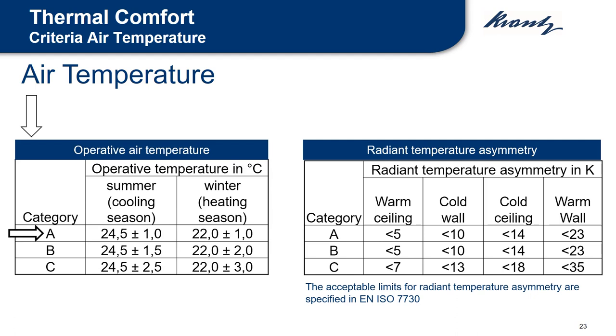In the right table, we can see the allowable radiant temperature asymmetries, likewise according to the classifications A, B, and C. For example, looking to the operative temperature table according to category A in summer, the ambient temperature should vary between 23.5 to 25.5 degrees Celsius, and in winter between 21 and 23 degrees Celsius.